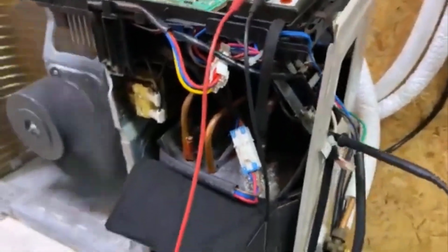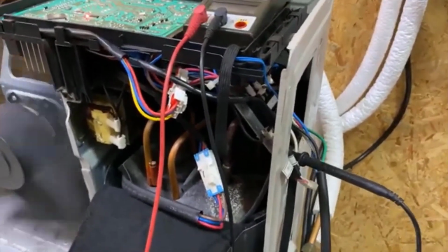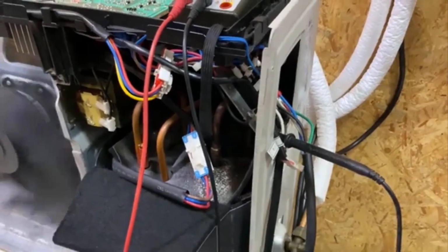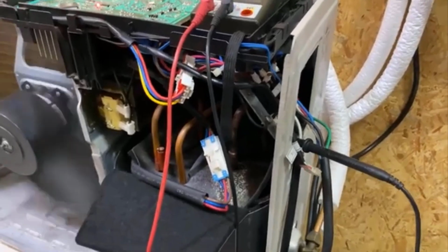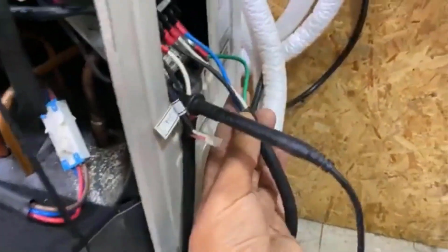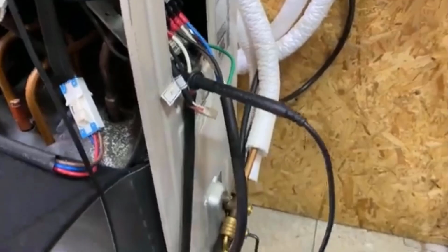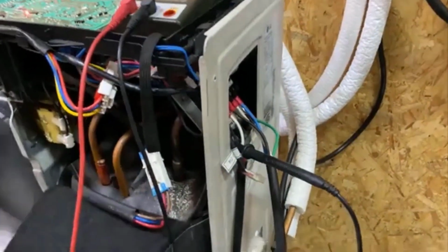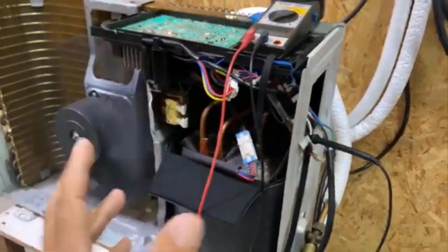Check electrical connections. Inspect interconnecting cables, and make sure the wires are correctly connected to the terminals indicated by the manufacturer: L, N, S, etc. Test cable continuity. Use a multimeter to check that the wires are not broken. Check polarity. Make sure the positive and negative poles are correct.